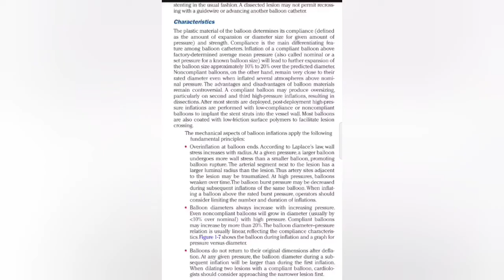Inflation of a compliant balloon above the factory-determined average mean pressure, also called nominal or set pressure for a known balloon size, will lead to further expansion of the balloon size approximately 10 to 20% over the predicted diameter. Non-compliant balloons, on the other hand, remain very close to their rated diameter even when inflated several atmospheres above nominal pressure. The advantages and disadvantages of balloon materials remain controversial.